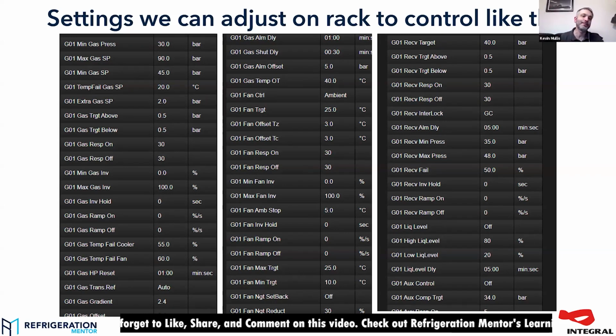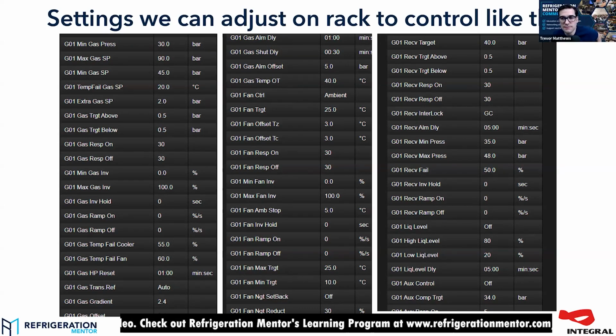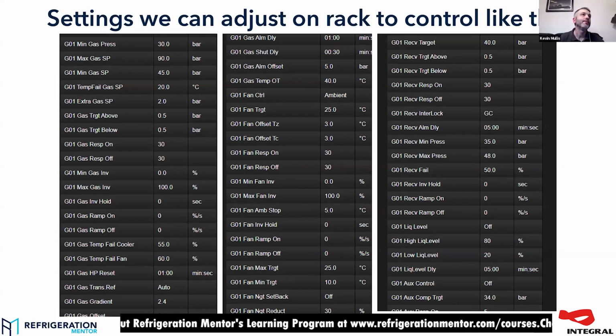It's not going to be super stable for temperature, but you can let the suction pressure come up 1 or 2 bar if that's better for the rack control in some setups. Yeah. You've got to find what works for your system. If it's a huge cold store evaporator, a short period to let the rack stabilize on its own without banging compressors in or out is better than having it panic and fight the coolers on the other end of it. Like I say, if it's a supermarket where loads are changing in little chunks, then yeah, you might need it to be a bit more stable on the suction pressure, but you need to understand your setup and then understand what is driving instability in it.